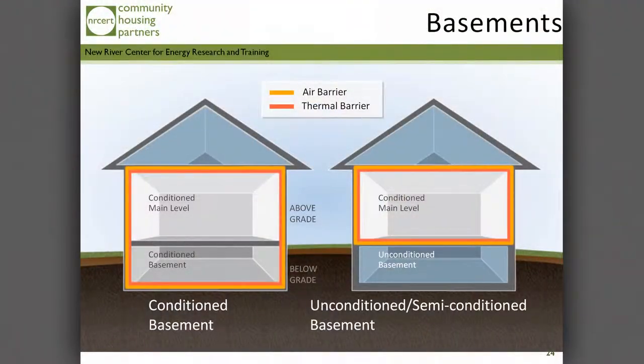If there's a living space down there — couch, futon, somebody's actually living there — and the system is sized appropriately and accounted for that space, then yes, it should be inside. But if it's supposed to be inside, what should the zonal pressure across that plane be? Zero.